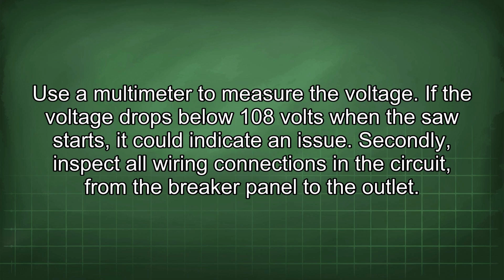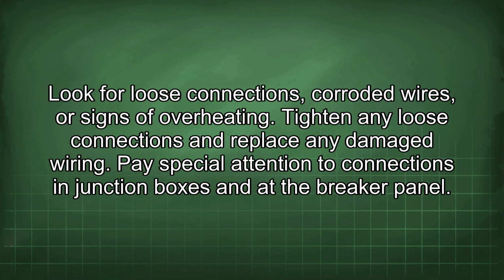Use a multimeter to measure the voltage. If the voltage drops below 108 volts when the saw starts, it could indicate an issue. Secondly, inspect all wiring connections in the circuit, from the breaker panel to the outlet. Look for loose connections, corroded wires, or signs of overheating. Tighten any loose connections and replace any damaged wiring. Pay special attention to connections in junction boxes and at the breaker panel.